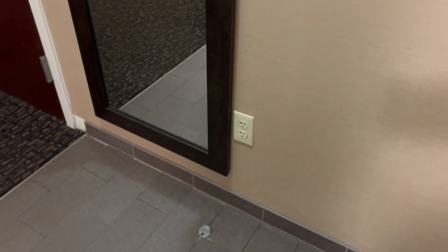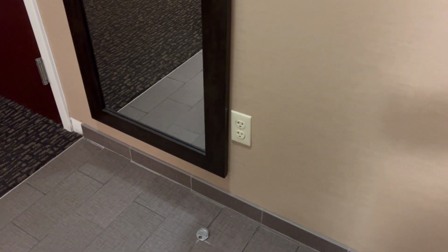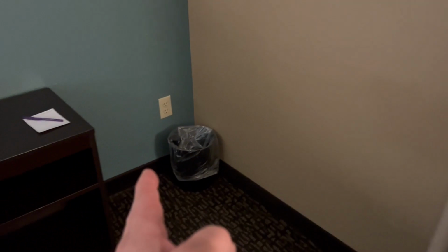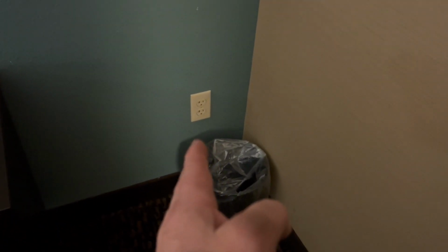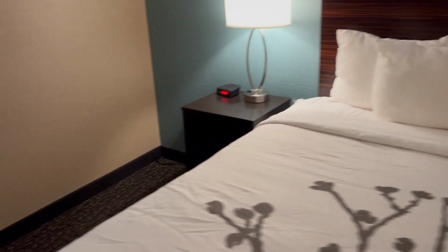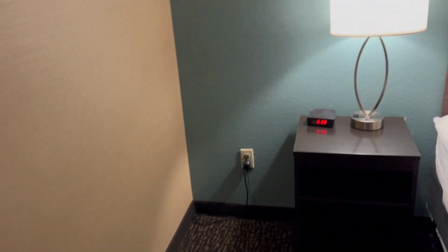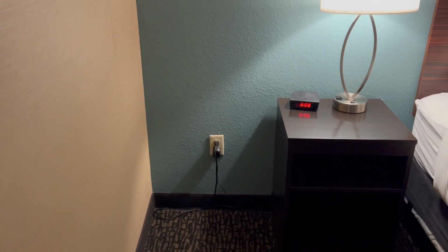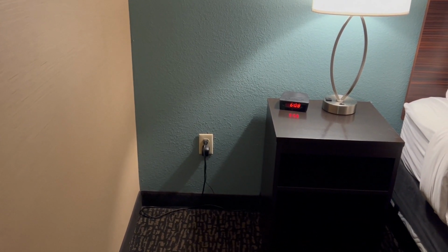That looks like it's readily accessible to me. I don't have to bend over or crawl under something or use a portable ladder, so that's readily accessible. And then I'm going to say that this receptacle outlet, that's readily accessible. And again, you can look in your code book under Article 100 for the definition of readily accessible. And that one looks like it's readily accessible. So I'm counting a total of 3.